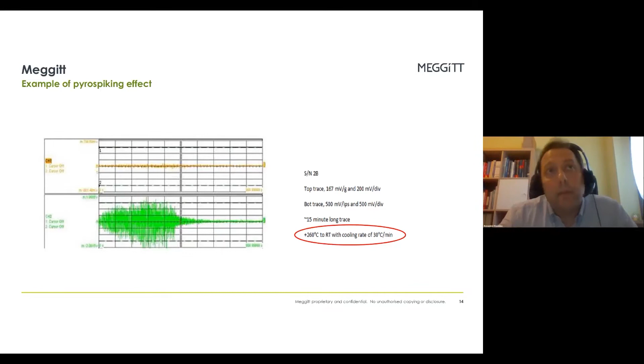The benefit of this feature is visible in this plot, a time history of acceleration over 15 minutes. The top plot is an acceleration time history, and at the bottom is a velocity time history, an integration of the signal. What happens during the pyrospiking effect is that residual charges move inside the crystal, bringing up a noise problem. This usually happens during cooling sessions of a test or a turbine cooling down.